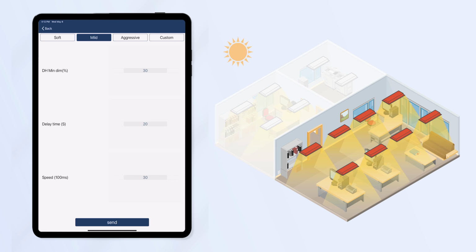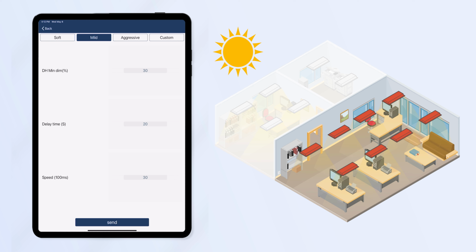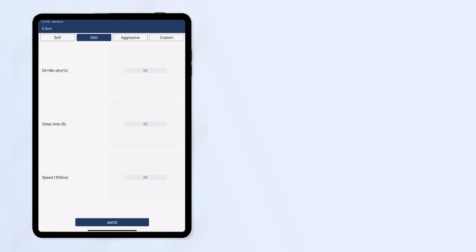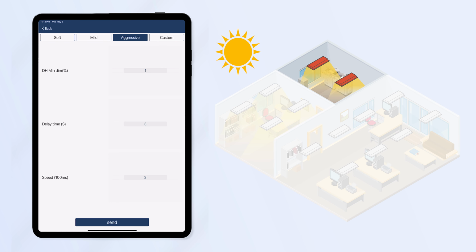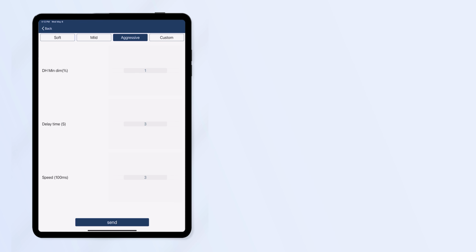Mild is more of a medium response time. Well suited to an open office, classroom, or meeting room. It has a minimum daylight harvesting light level of 30%. Aggressive has a quick response time, which would be well suited to a tea room, storage room, or warehouse space. The minimum daylight harvesting level is equal to the low-end trim, about 1% to 10%. Custom allows the user to fine-tune the daylight harvesting parameters.